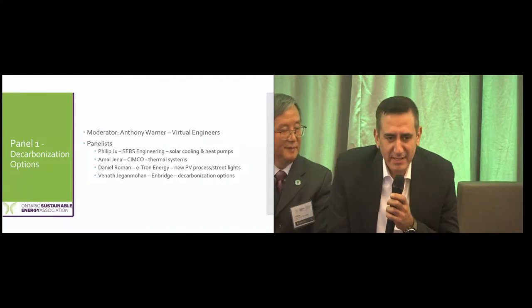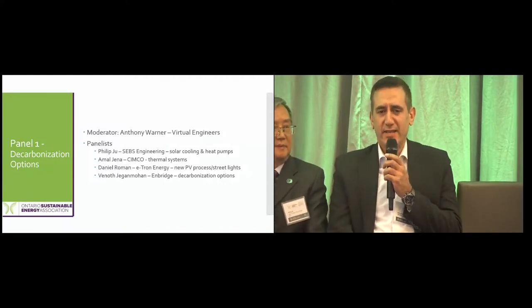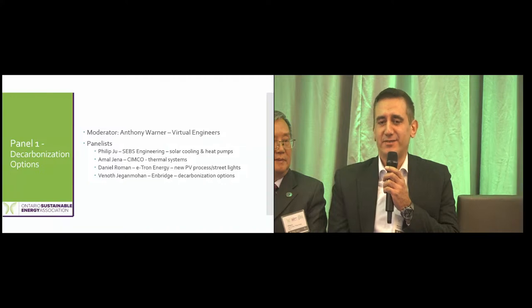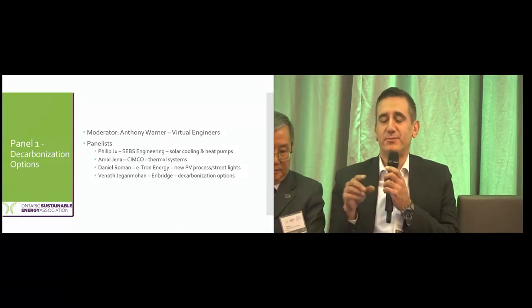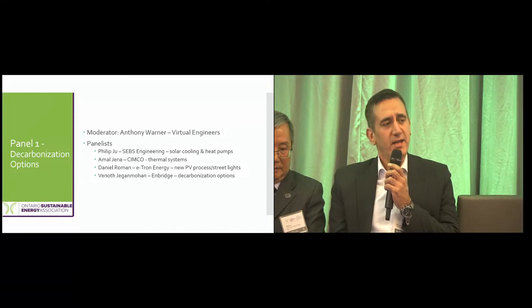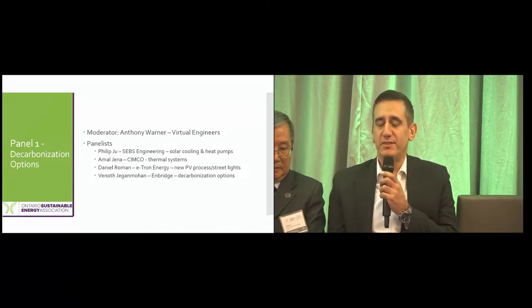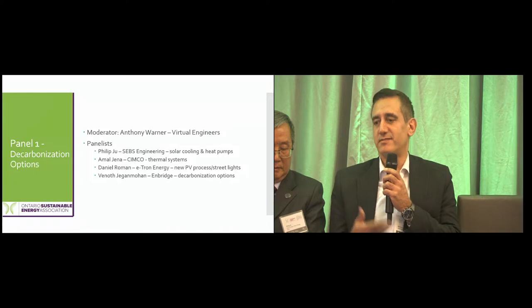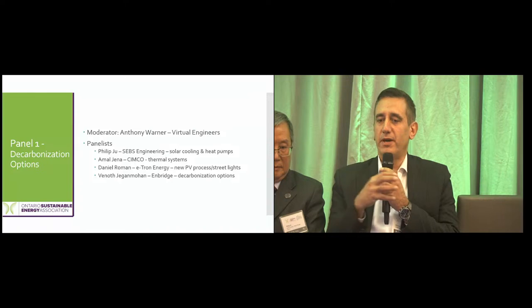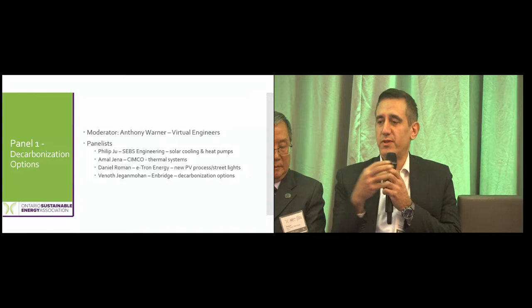As you know, vacuum tube collectors are well known but less popular in Canada because of cold weather, and some believe that because of cold weather we may lose lots of heat. But those vacuum tube collectors actually collect over 90% of the energy of the sun as heat, so this is really a very good thing. On the other hand, PV panels are already very well commercialized and used in our buildings, with efficiencies of about a maximum of 23%. So the idea is to combine these two in a single system called a hybrid PV thermal system, generating both in the same setup.